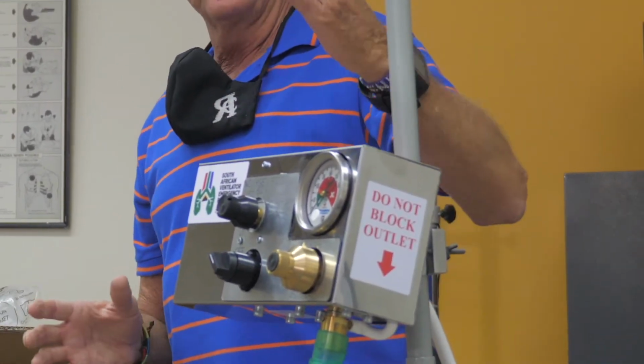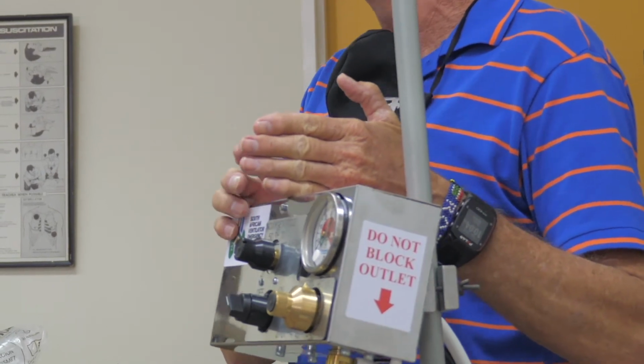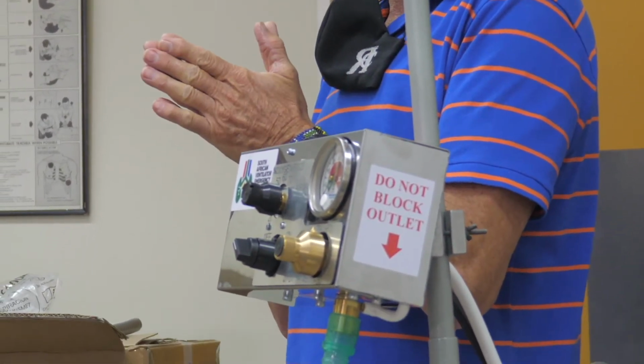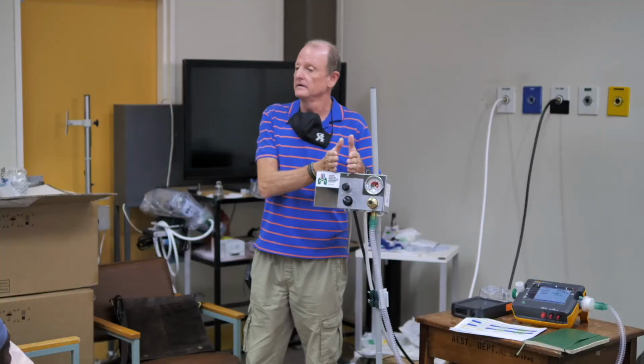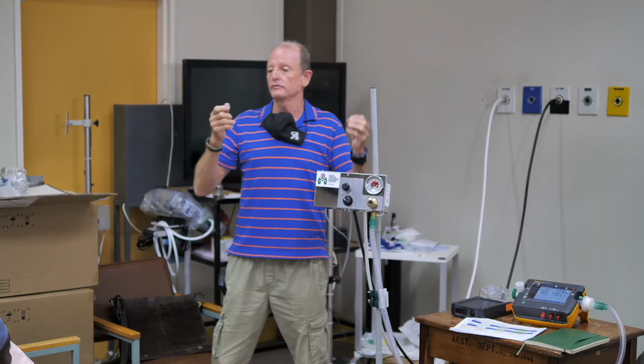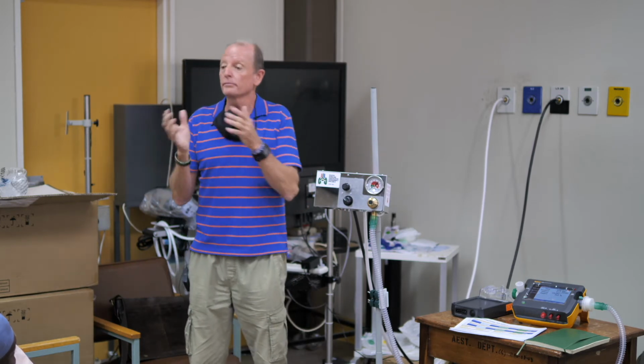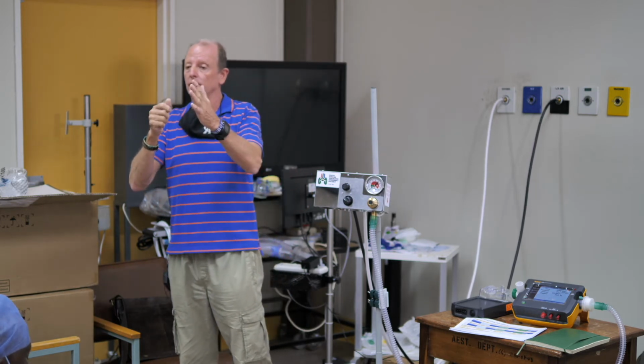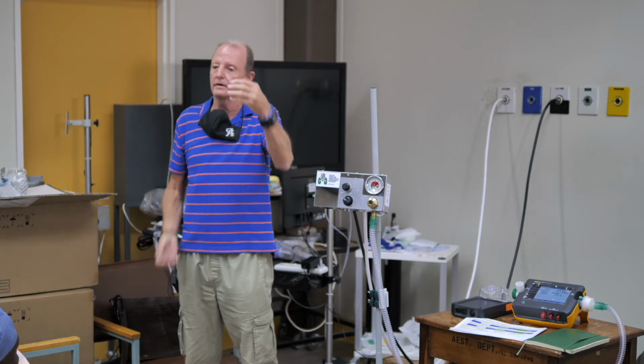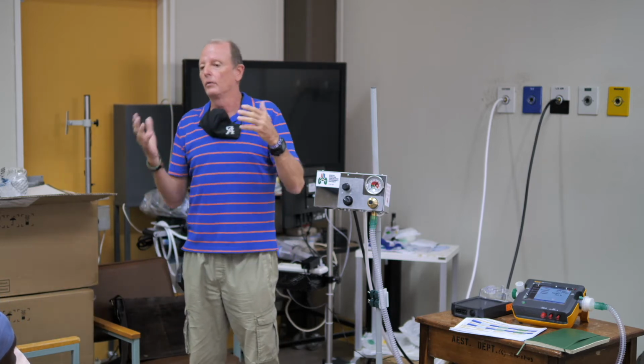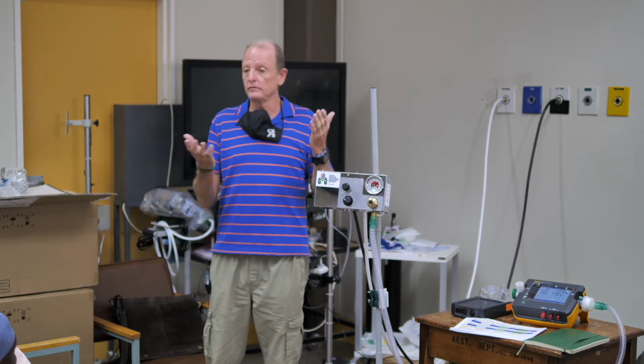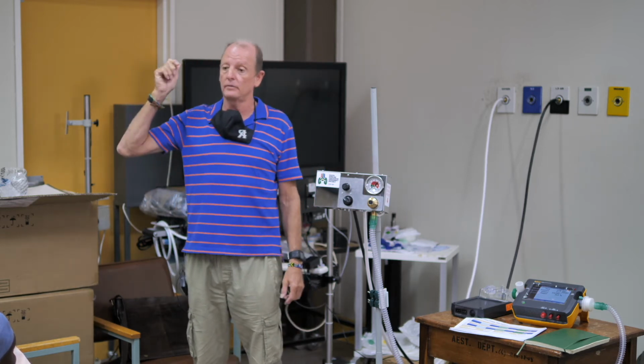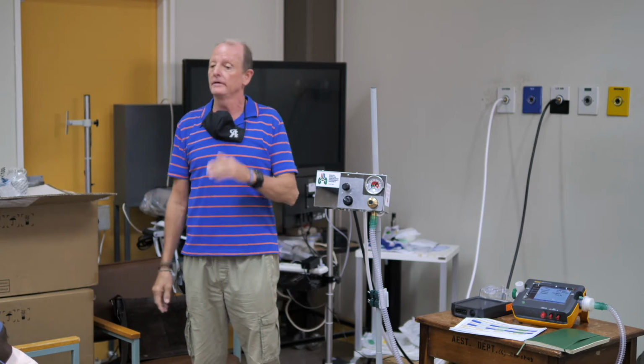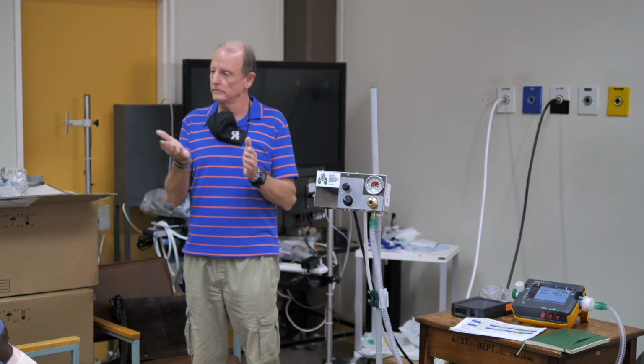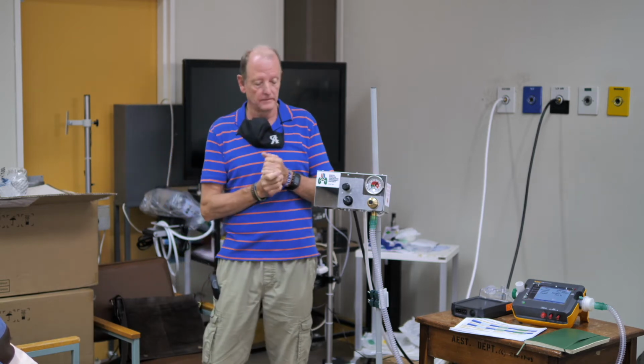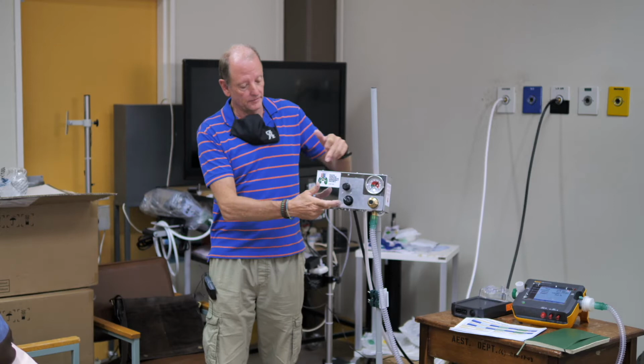In here, the main device inside this unit is an oxygen-air blender. That is your driving factor here, so you don't have to worry, as with an entrainment system, a Venturi system, about what percent you are going to get if someone blocks the Venturi, or dirt gets in the Venturi. Here you've got a blender: if I want 21%, I get 21%. If I want 100, I get 100. It's just easier for your patient. All that flows down through to the on-off switch.